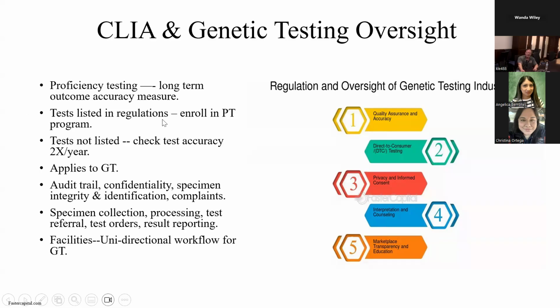I mean, you have to enroll in a testing program, which means that twice a year, we have a company that sends us samples. They're unknown. We don't know what they are. And they say, here's your samples. And we're supposed to figure out what they are, test them, get the result, and then send them back. So it's called proficiency testing. And we get this done every quarter.